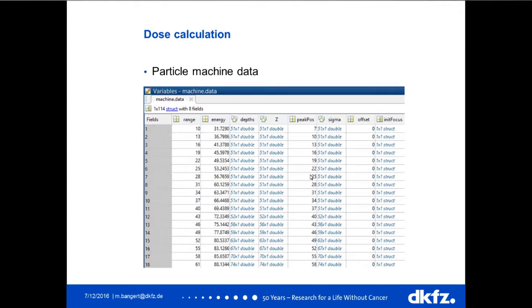If you want to get your own machine into Matrad it's quite straightforward because of our descriptive data format. The machine data for our proton machine shows one column describing the range of the particles, the energy, depth dose curves, lateral sigmas in a table, and the initial focus size stored in a structure because we model beam broadening in air. You just have to get your data in a similar format and then you can use this machine data directly for treatment planning in Matrad.